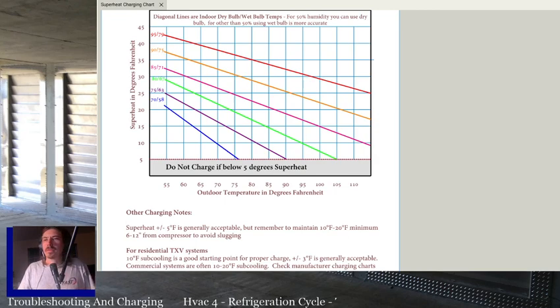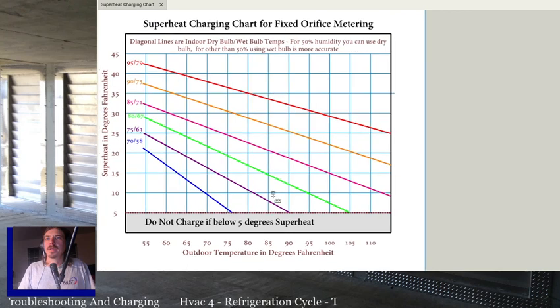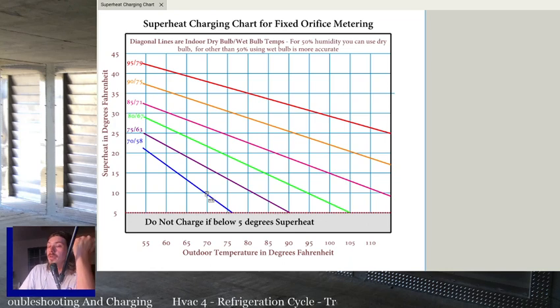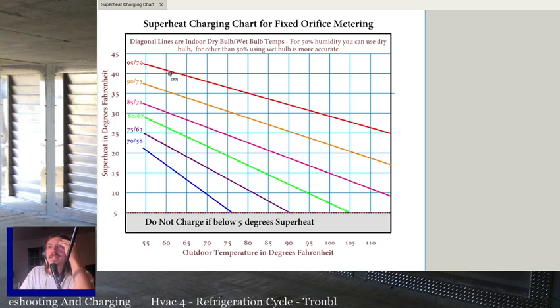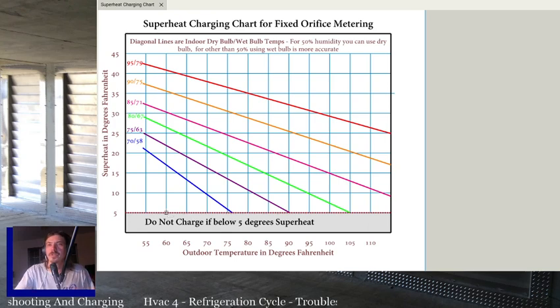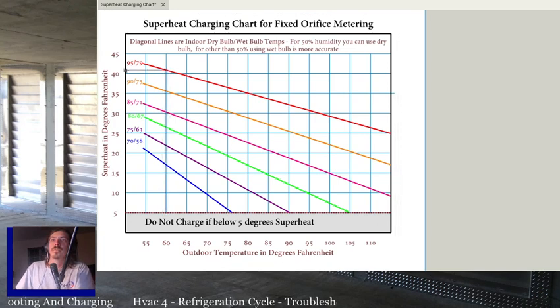All right. So what I was talking about, if the indoor temperature is low and the outdoor temperature is high, repeat that. Okay. If indoor temperature is high, like if you're looking at this chart, let's say it's 95 degrees inside. If it's 95 degrees inside and 60 degrees outside, your superheat's going to be through the roof. You see that line? So here, I'll even draw a line for you real quick. See, we come up here, and we're at 42 degrees superheat.